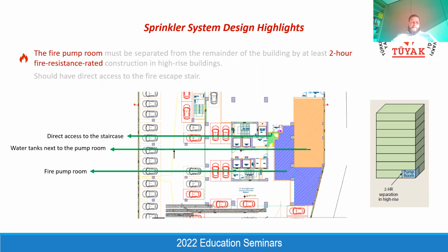And the third one, but I think it's the most important one, the fire pump room shall have direct access to a staircase. Most of the architects do not understand the main reason for this requirement, but the fire pump room shall be kept accessible in case of fire in the building. It means even if we have a huge fire, even if we have a large fire incident within the building, we need to reach the fire pump room to check whether the pumps are working as required, or maybe we need to start these fire pumps manually. That's why even if the building is burning, I'm exaggerating, even if half of the building is burning, we need to access this fire pump room.